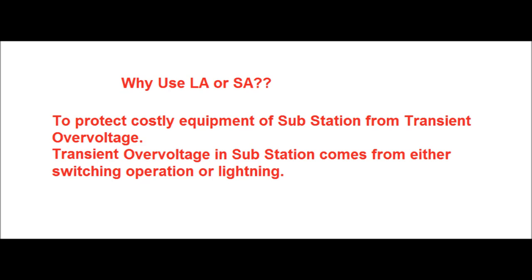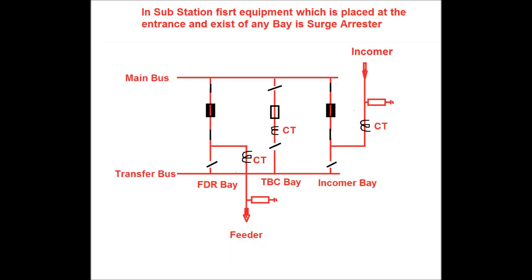Lightning arrester or surge arrester in a substation is used to protect costly equipment from transient overvoltage. This transient overvoltage comes either from switching operations or from a direct stroke of lightning. In a substation, the first equipment placed at the entrance and exit of any bay is the surge arrester. A single line diagram with one incomer, one outgoing feeder with a bus coupler bay, one main bus, and one transfer bus has been shown.